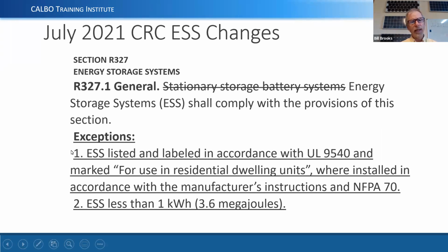Now, there's a basic exception that is very confusing, and I don't like the language. I just want to explain it to people that are maybe confused by it. ESS listed and labeled in accordance with UL 9540 and marked for use in residential dwelling units do not have to meet any of the requirements of R327 in the California Residential Code. Okay, there are exactly zero products that meet this requirement. I call this the unicorn mark. Nobody has this unicorn mark, and nobody's seen this unicorn mark because it's a unicorn.